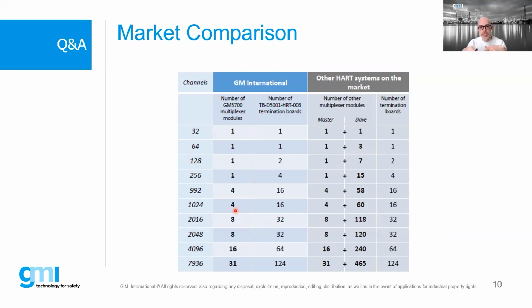This is thanks to the fact that the GMI multiplexer system does not need to use a slave device for its functionality. In fact, what for the competition is a fundamental device is integrated into the HART termination board in the GMI system and is therefore managed channel by channel. This allows us to have a more flexible system with fewer devices involved in signal management and therefore with great saving in terms of engineering cost.